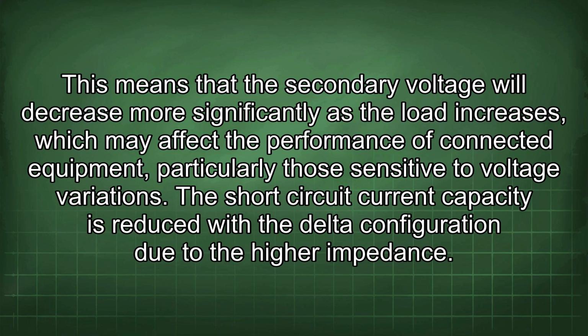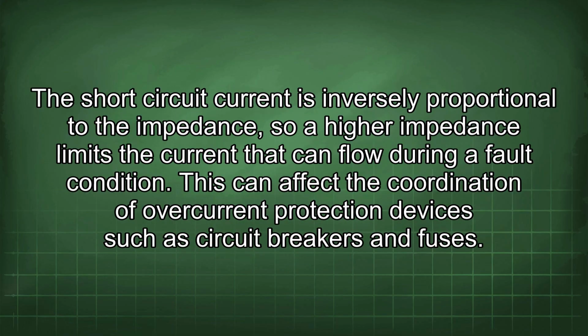The short-circuit current capacity is reduced with the delta configuration due to a higher impedance. The short-circuit current is inversely proportional to the impedance, so a higher impedance limits the current that can flow during a fault condition. This can affect the coordination of overcurrent protection devices such as circuit breakers and fuses.